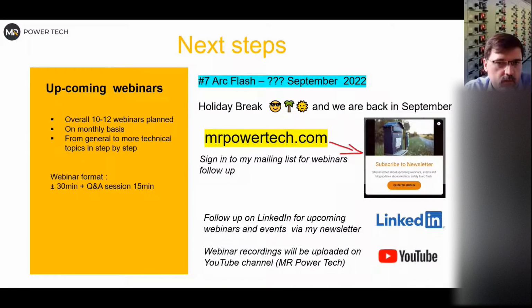It's more for engineers to explain when they do a study, but I see very often that people refer to an arc flash study using PPE categories 1, 2, 3, 4. It's clearly written in NFPA that you cannot do that - you have to follow a different table, which is up to 12 calories and above 12 calories per square centimeter. There are no categories there, it's like 2 levels, driven purely by the incident energy results.